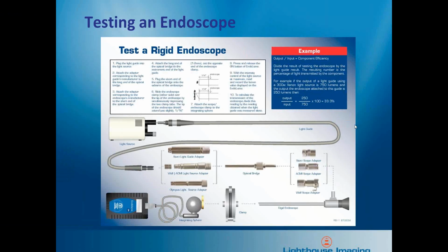Great, then if we flip back, we'll see that the final measurement that we're going to make is testing an endoscope output. Here there's a little bit more detail, and again the graphic walks you through how to set this up. The light cable goes into the light source, use the correct fitting. Now we use the correct fitting to attach to the endoscope, and then we place the tip of the endoscope inside the clamp system that comes with the EndoLume.